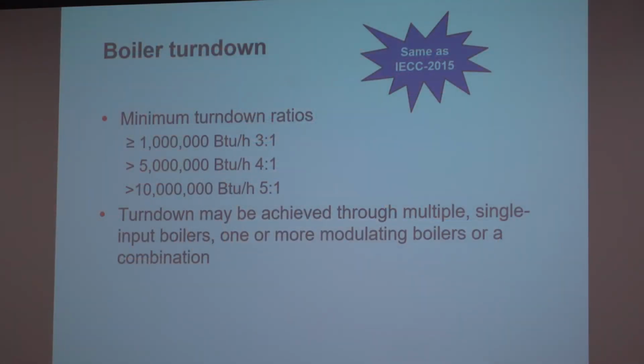If you did still have a belt-driven fan for whatever reason, I can't imagine, but if you still do on a new product, you're going to have to do some sheave adjustments there. Boilers have better turndown requirements. You can do that either by a combination of better burners that have more controllability, or by using staged boilers that have, in the collective, the same turndown effect. And that is the same.